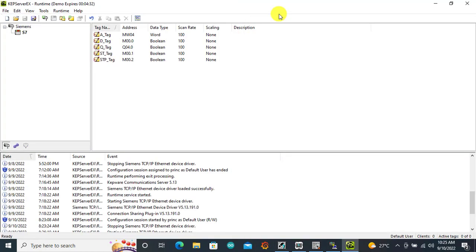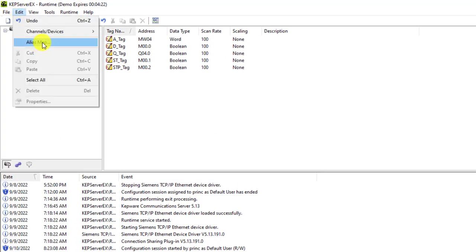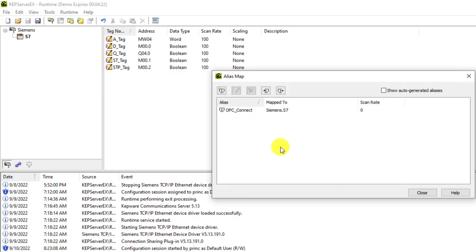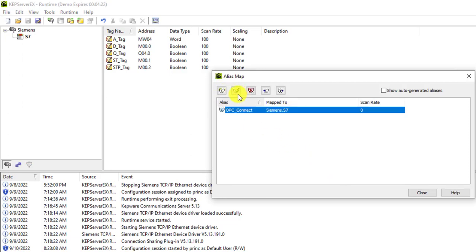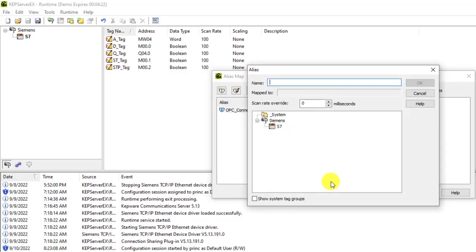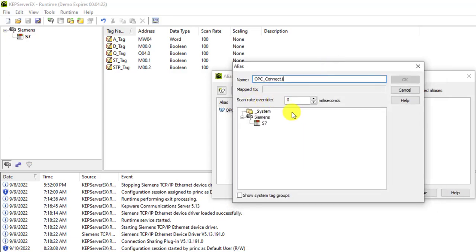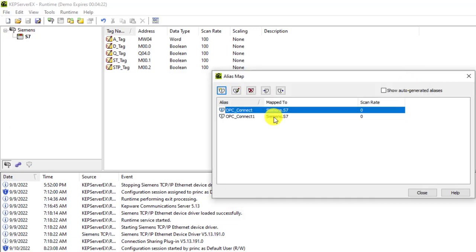Now let's do the link between the OPC and the IntelliSCADA software. With all tags tested, we will now link the OPC server with the SCADA software. To do this, go to Edit and come to Alias Map. You need to create a connection. I've created one already; let me create one more. Go to New, give it a name — OPC_Connect1. Then map it to the S7 and click OK. Our connection is created.